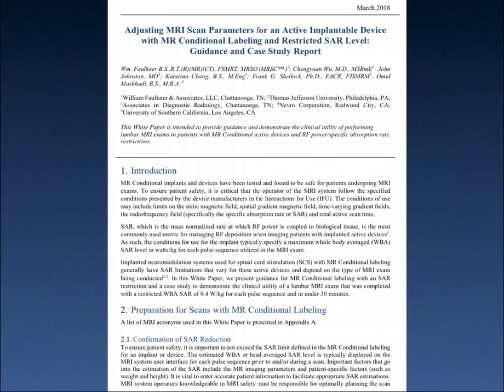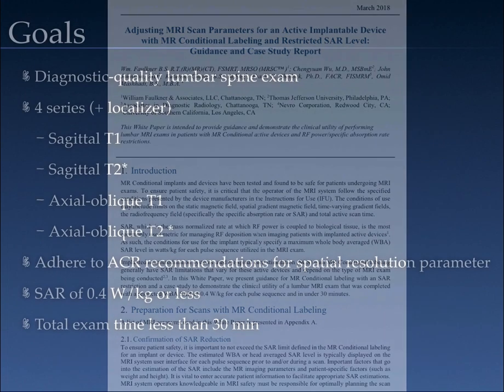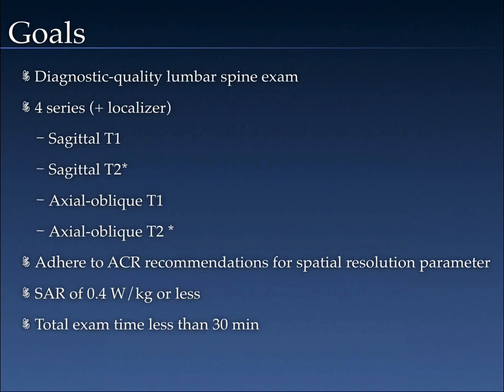The images and data in this video are from a white paper that I co-authored for NEVRO, and I'd like to thank NEVRO for their permission to use this case study for this SMRT video. The goal here was to acquire a diagnostic quality lumbar spine exam. We wanted to match not only the ACR recommended spatial resolution parameters but also the contrast parameters — a sagittal T1 weighted sequence, a sagittal bright fluid sequence using a sagittal T2 star weighted sequence, an axial oblique T1 weighted sequence, and an axial oblique T2 star sequence. The whole body averaged SAR would be 0.4 watts per kilogram or less, and our total scanning time needed to be less than 30 minutes.